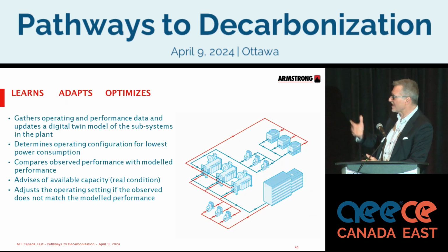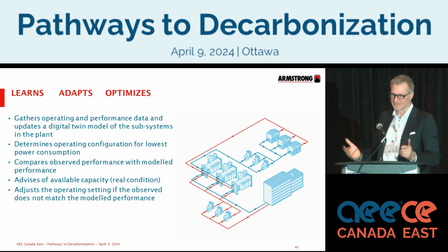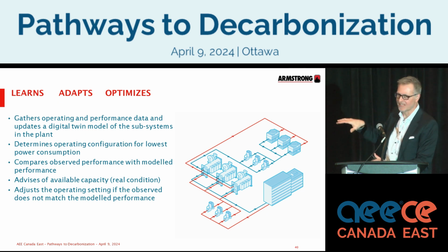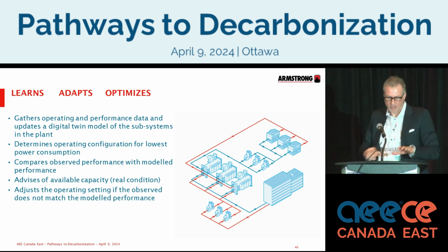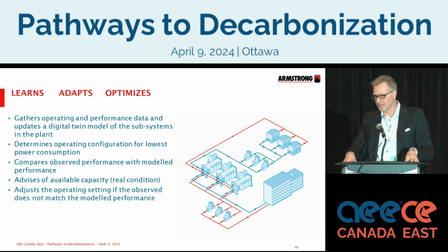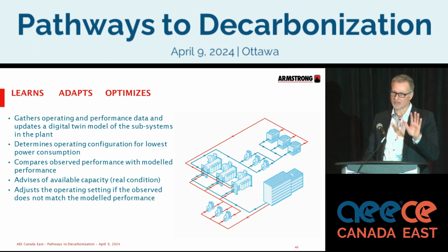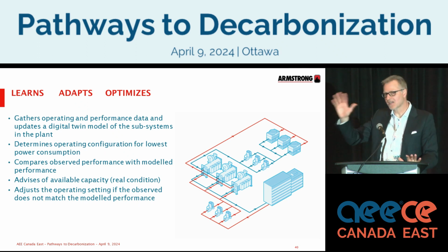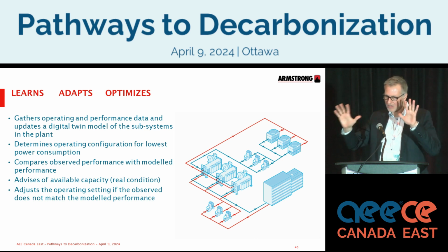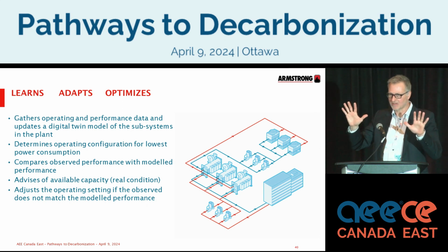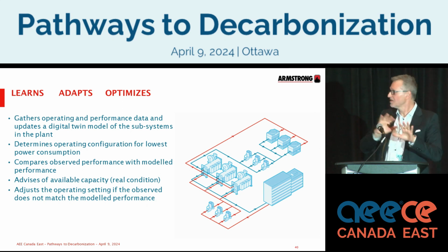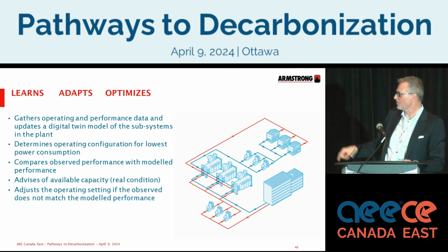It's gathering operating and performance data. Everybody wants data. Now remember we showed the original performance maps. The way the system is first set up is that you set up your performance maps based on published data. The system starts operating, you have a digital twin, and you look at the actual performance of the equipment. Now you're cross-referencing: is the data in alignment? If not, do we update those performance maps? We continuously do that. We compare the observed performance and the modeled performance, and it advises the availability of capacity in terms of real conditions.